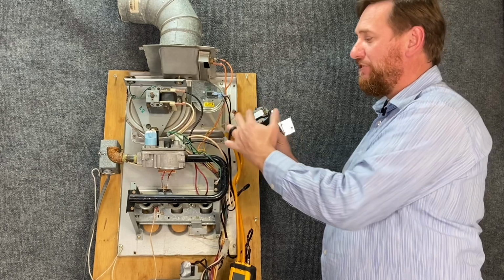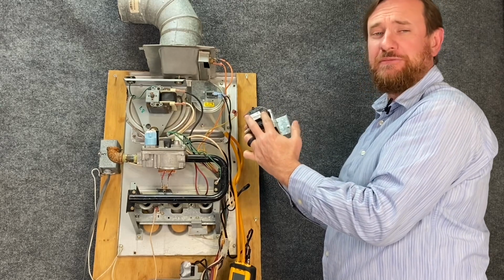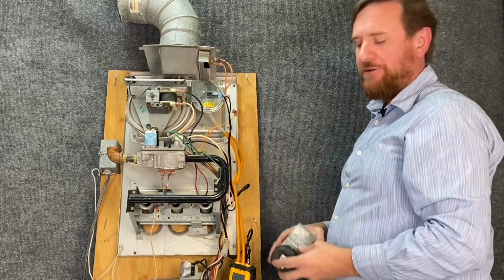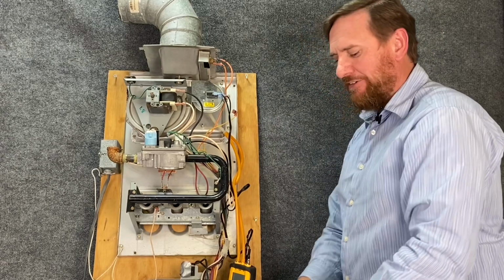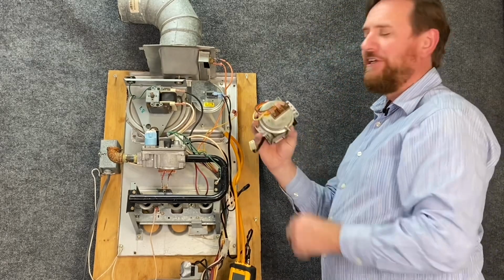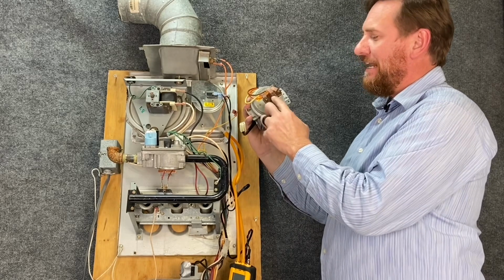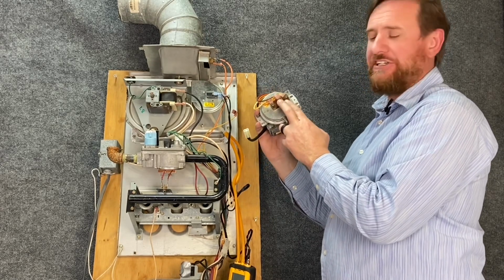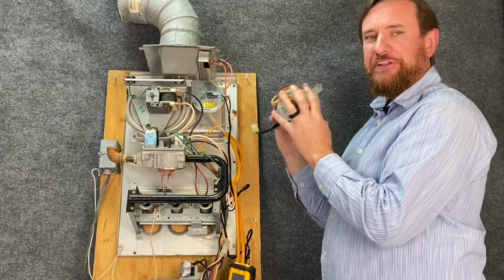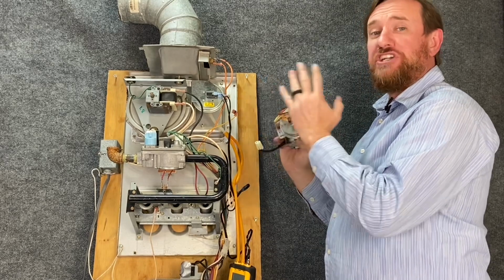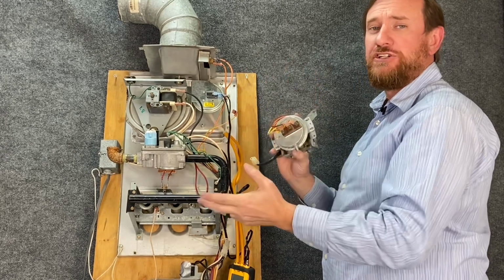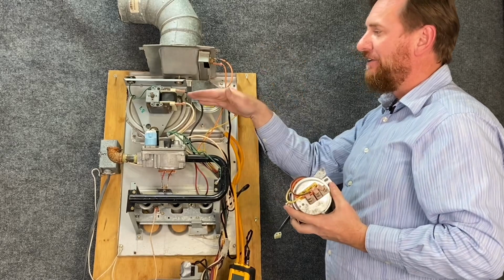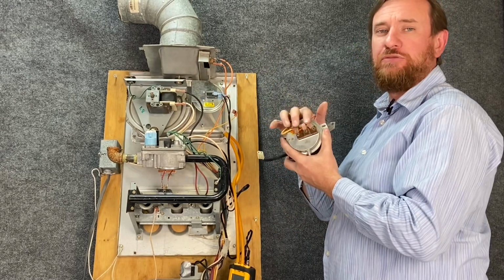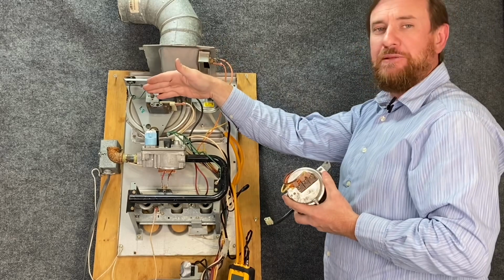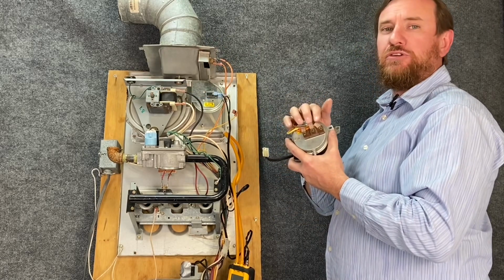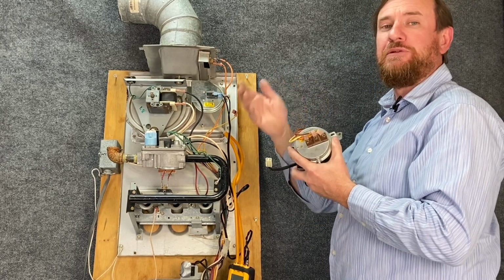If I check it on the unit, I have 24 volts or some kind of voltage. But not all of them are normally open. They do make some that have normally open and normally closed connections, such as this one. The control board for this particular unit wants to know that the switch is for sure closed and for sure open. In other words, right now the system is off. It wants to know that that switch is closed, and when the system came on and pulled the proper vacuum, the normally closed would open, the normally open would then close.